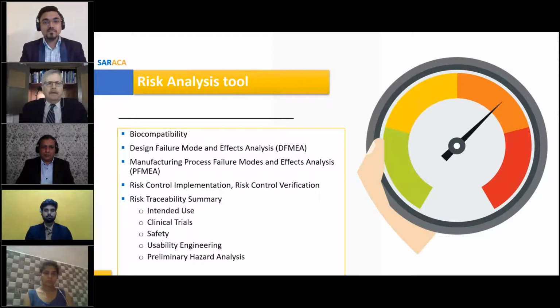I would just like to add a caution to this. Recently, I've been asked by auditors about biocompatibility. In the past, it's been relatively well defined that biocompatibility pertains to whether your device comes in contact with the patient, how long it's in contact for, and what manner of use, such as abraded skin or through the skin. However, the auditor of the tech file was very specific, and he wanted us to take into consideration biocompatibility as it relates to the operator of the device.